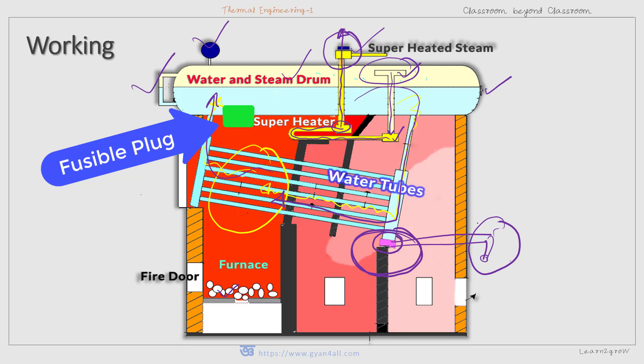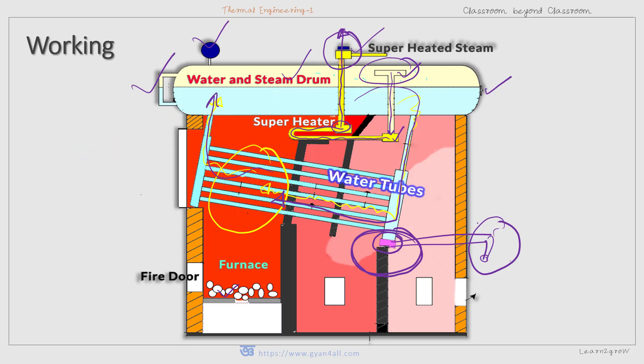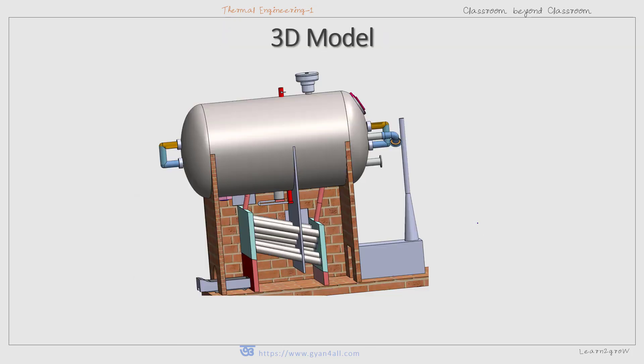In the Babcock and Wilcox boiler, water passes through the tubes which are heated by combustion gases. There are two headers: the downtake header and the uptake header. Steam goes to the drum through the uptake header, and water comes back down through the downtake header, establishing natural circulation. The 15-degree inclination of the tubes is essential for effective convective current. Finally, a 3D model will further clarify the working principle of the Babcock and Wilcox boiler.